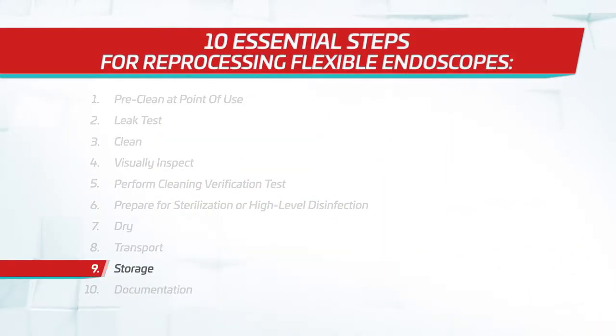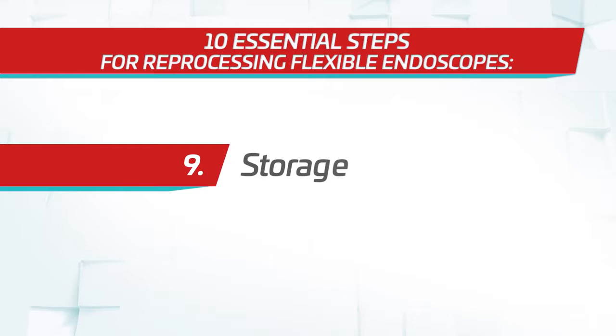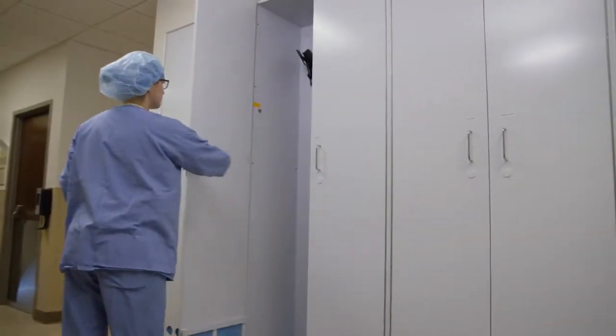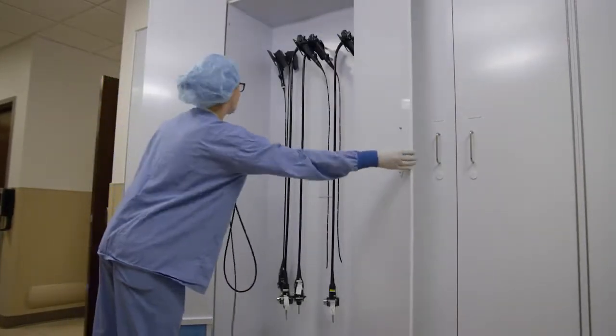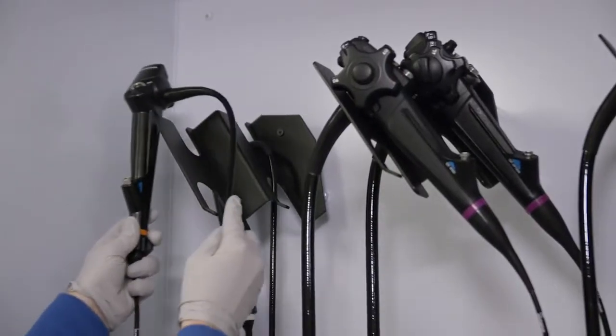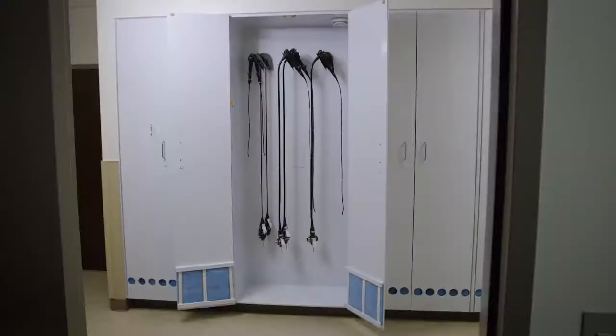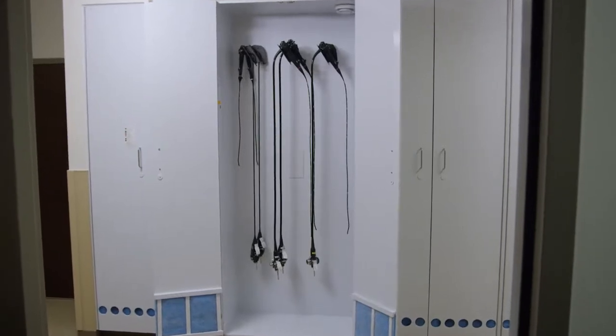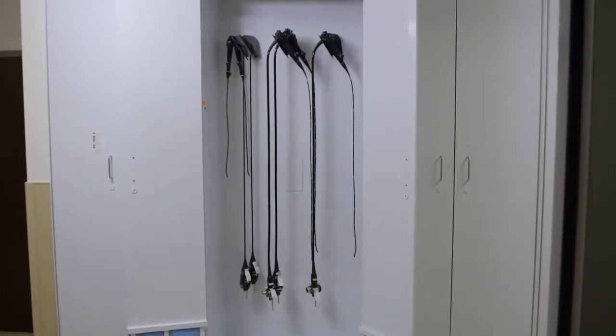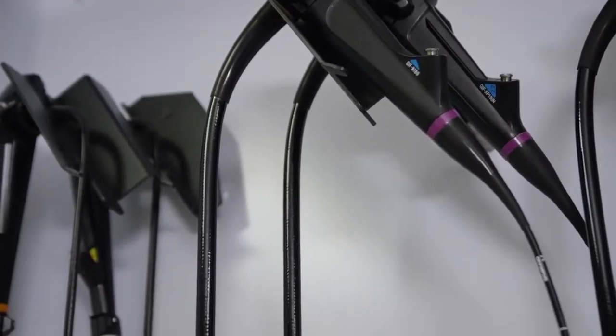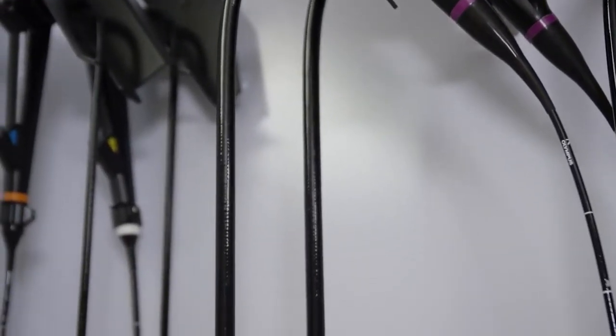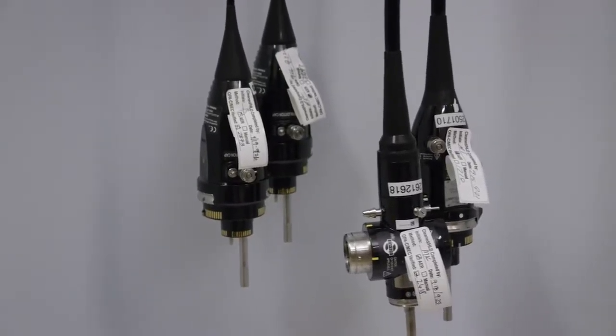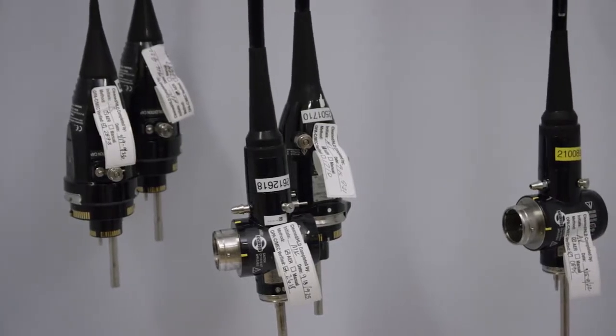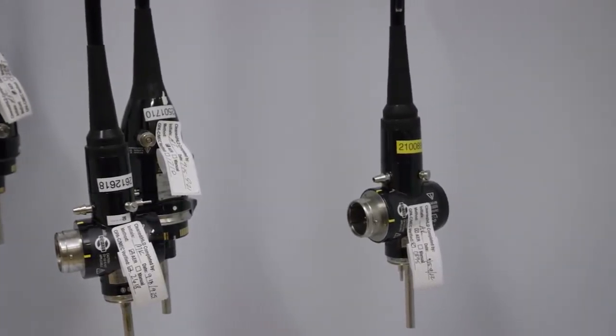Ideally, store the scope in cabinets that continuously circulate HEPA-filtered air around scopes and through channels to remove any residual moisture. At a minimum, store according to the endoscope IFU in a manner that prevents recontamination, protects from damage, and promotes drying. The storage cabinet should allow the scope to hang vertically with the distal end hanging freely, without coiling or touching the bottom of the cabinet. Horizontal drying and storage cabinets are also available. Make sure the angulation lock is in the open position, and if there are reusable, removable parts such as valves and caps, keep them in a small container with the scope.